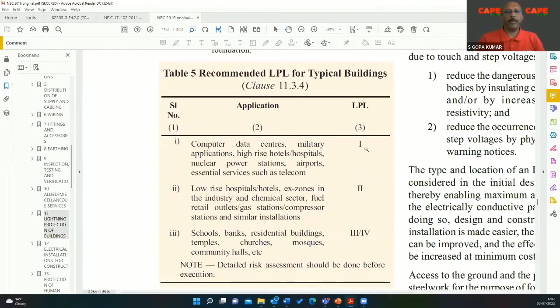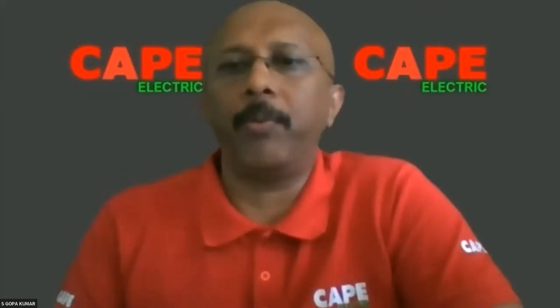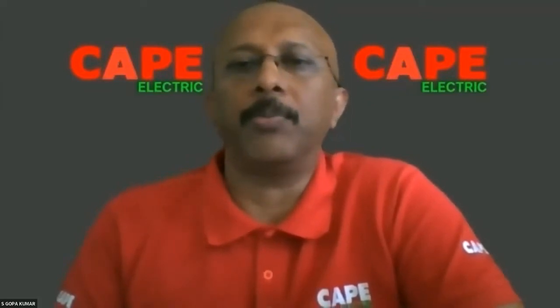Computer data centers and military applications require Level 1. Low-rise hospitals and EX zones (Zone 2) are next. Schools, banks, and residential buildings fall under Level 3 or 4. This is a typical guide. You can also do a risk assessment — we send an Excel sheet, you fill it in, we make the calculations and tell you what minimum protection is required. Either go as per the NBC recommendation or perform a risk assessment.